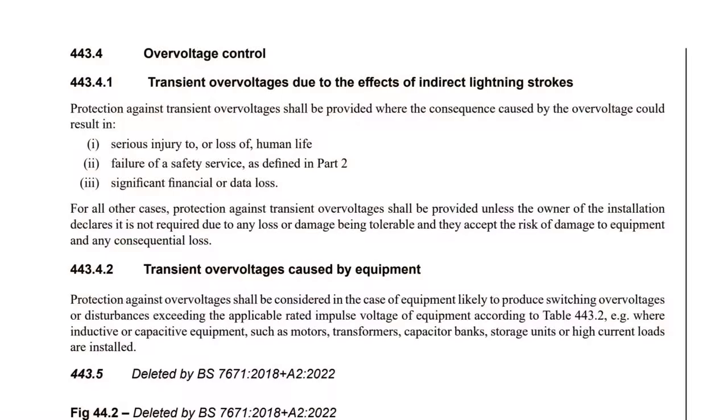Now regulation 443.4.1, which covers transient overvoltages due to the effect of indirect lightning strokes, states that protection against transient overvoltages shall be provided where the consequence caused by the overvoltage could result in: one, serious injury to or loss of human life; two, failure of a safety service as defined in part two; three, significant financial or data loss.